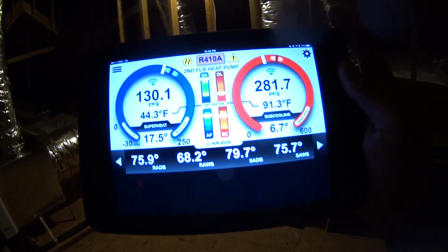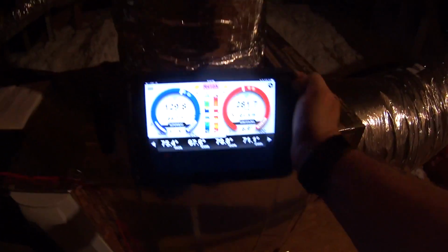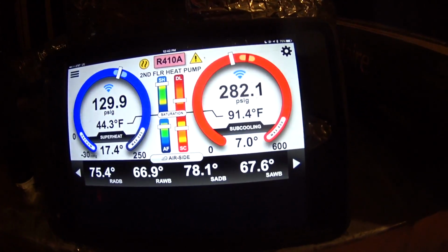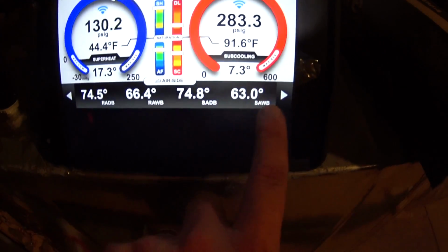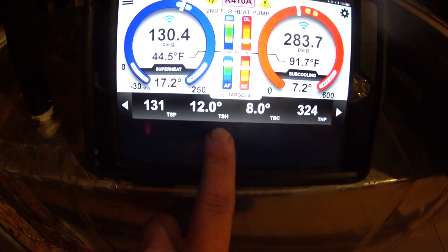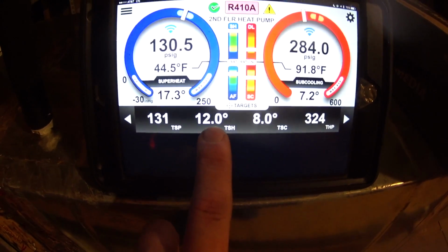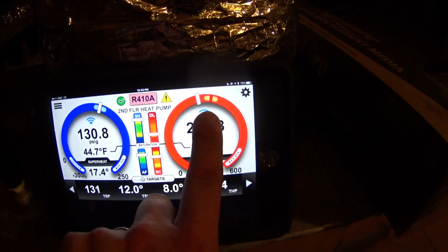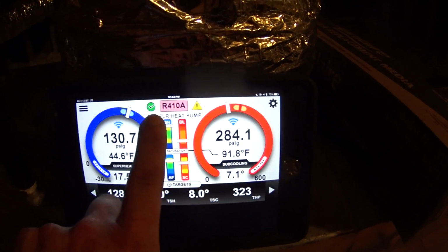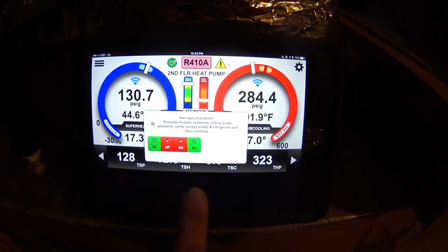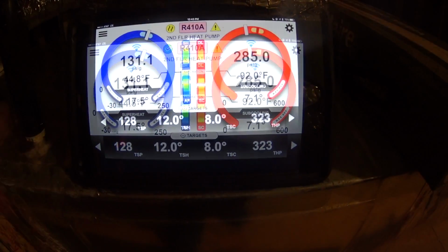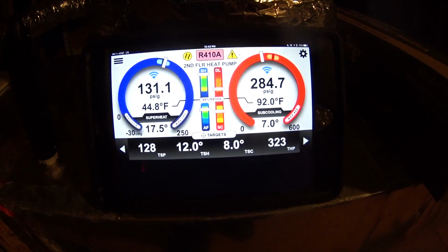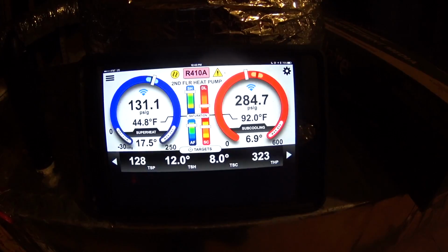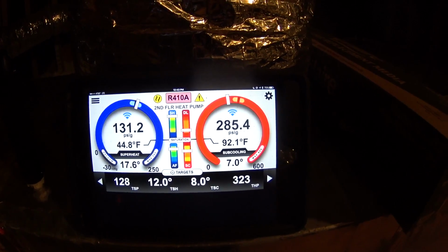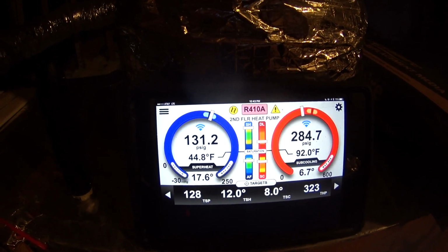And then we've got the refrigerant probes already up. The target subcooling is 8 degrees. The 12 degree superheat target is an arbitrary target. Despite our head pressure zone being a little lower than the target, we've got a balance, and troubleshooting is not helpful at this point. It is damp outside. We've had a lot of moisture, some rain and humidity, so the head pressure being a little low is not surprising.